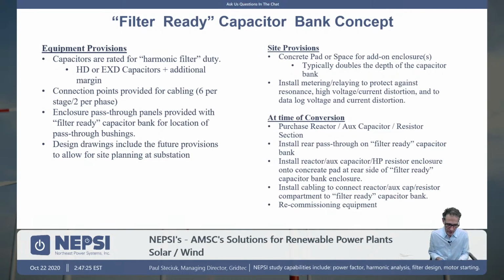Make sure that the substation layout drawings include the future filter bank. You've got to have space in there. If I have to convert this to a filter, I need space in that substation. Make sure it has a space. So this is pretty much standard for what NEPSI does for the metal-enclosed solution. We will show that space requirement in the substation to convert a cap bank to a harmonic filter bank.